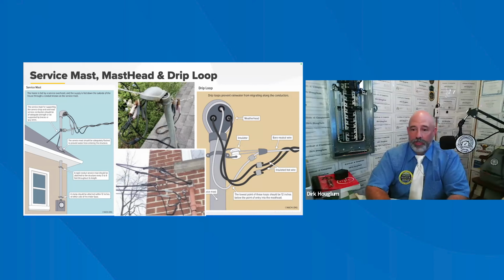In the middle of the top picture, the masthead and service drop has been damaged by a fallen tree branch. Not only was the masthead smashed, but the neutral conductor splice was torn apart and repaired with just jumper cables. Makes me laugh. The inspector should be reporting this. After the service mast, there should be a loop in the conductors. The lowest point of the loop should be 12 inches below the point of entry in the masthead. This is to prevent rainwater from migrating up the conductors or cable assemblies and pouring down into the masthead. This is a drip loop.